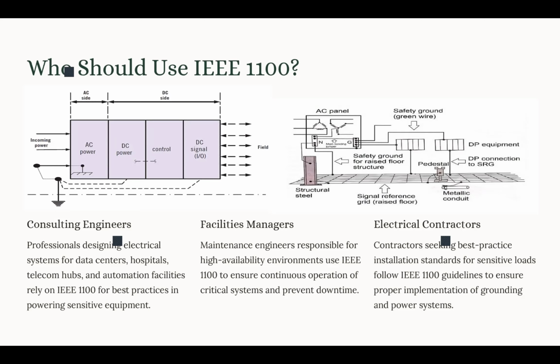Now, the third group of people that use IEEE 1100 are electrical contractors. When we talk about meeting the requirements of IEEE 1100, one thing is to design the system based on those criteria, but we have to pay attention to the fact that implementation of that design has a significant effect on the outcome of the whole project. So it's not just the proper designing aspect. We have to make sure the contractors implementing the designed power and grounding system also follow the requirements of IEEE 1100, to make sure they don't mess up the design that was given to them.